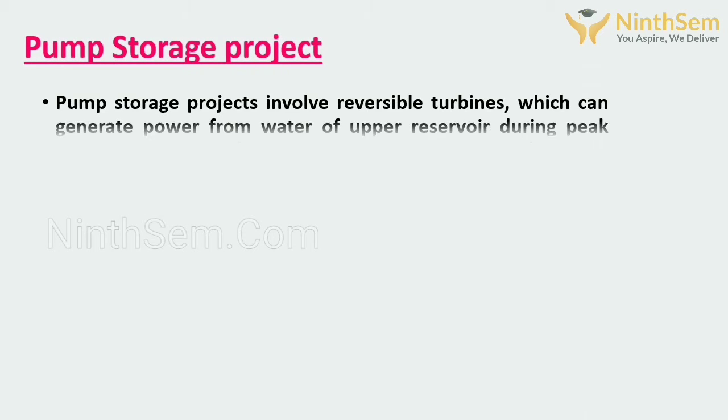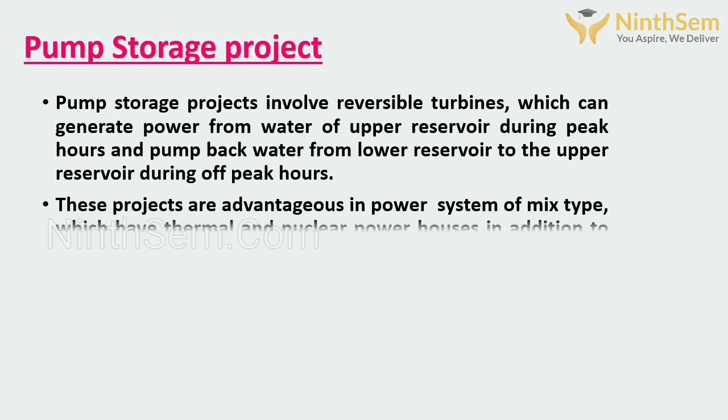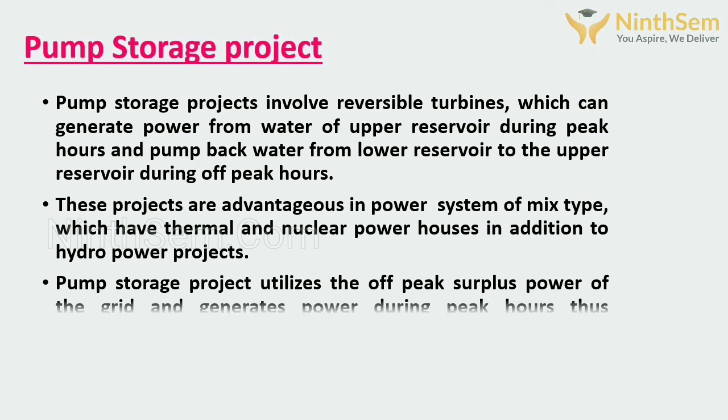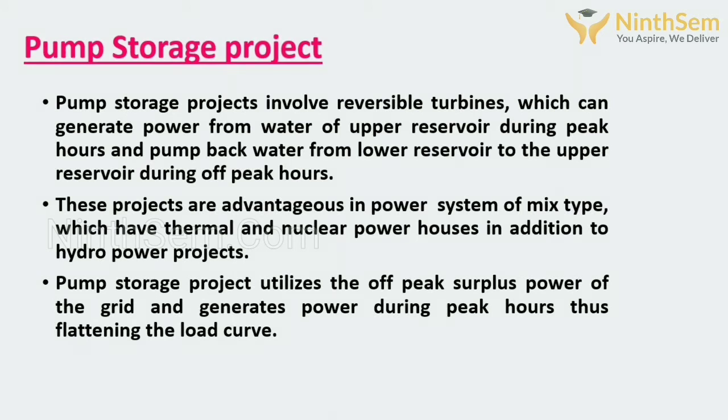While moving towards the pump storage projects, the pump storage projects involve reversible turbines, which make the generation possible from the upper reservoir during the peak hour and pump back the water from the lower reservoir to the upper reservoir during off-peak hours. The pump storage project utilizes the surplus power of the grid and generates power during peak hours, thus flattening the load curve.